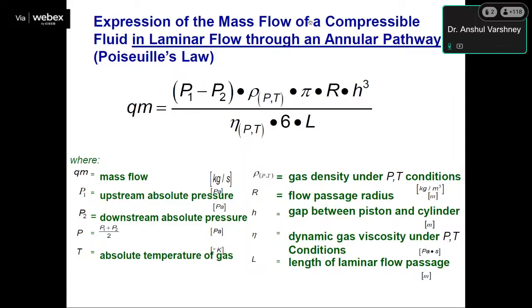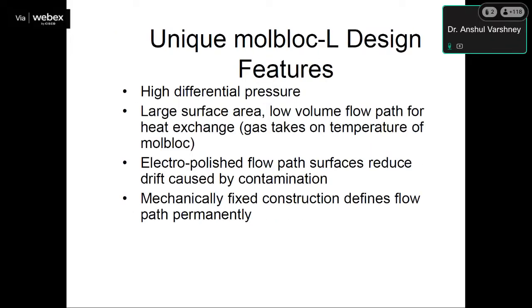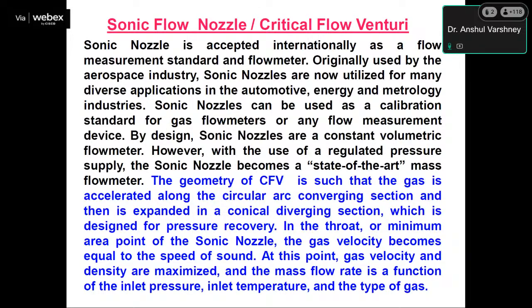This is the expression of mass flow of a compressible fluid in laminar flow through an annular pathway. These are some mathematical calculations. Basically, a sonic flow nozzle or critical flow venturi is used for the calibration. The sonic nozzle is accepted internationally as a flow measurement standard and flow meter, originally used by the aerospace industry. Sonic nozzles are now utilized for many diverse applications in the automotive, energy, and metrology industries. Sonic nozzles can be used as a calibration standard for gas flow meters or any flow measurement device. By design, a sonic nozzle is a constant volumetric flow meter. However, with the use of a regulated pressure supply, the sonic nozzle becomes a state-of-the-art mass flow meter.